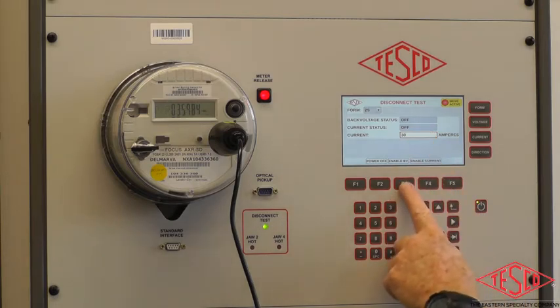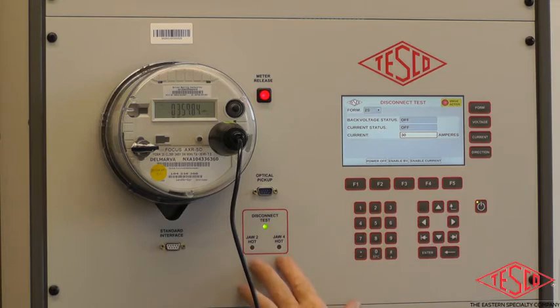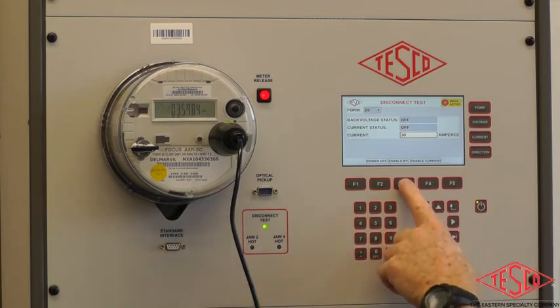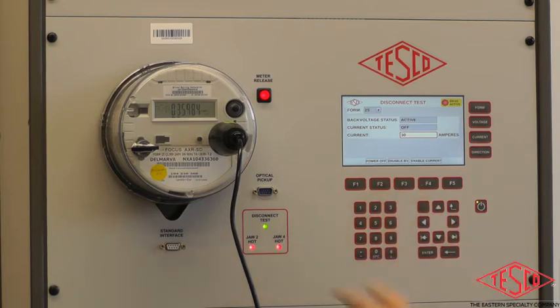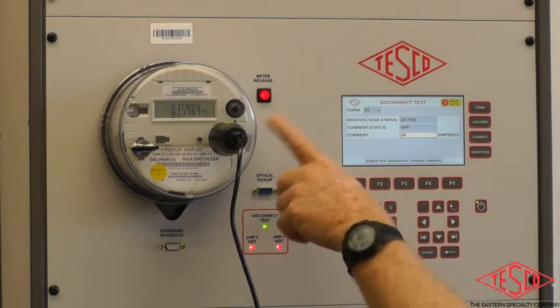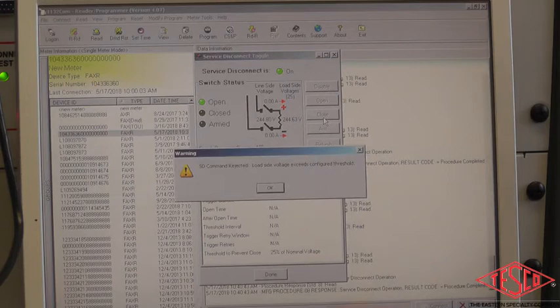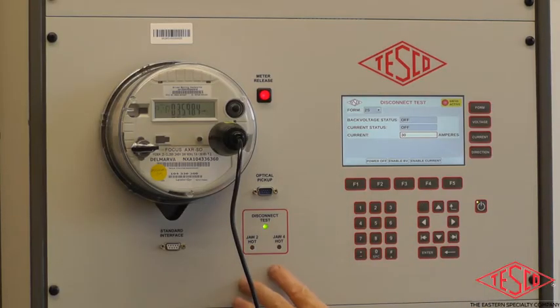So I'm going to enable the back voltage. You'll see the jaws will go hot because now it's simulated that the customer has put a generator or maybe an extension cord from their neighbor and is now applying their own power there. So this circuitry in the meter will see this, and if you try to close on it, it rejects it and says no, there's a back voltage. So now I can disable the back voltage. You'll see it'll return to the state that it would normally be in, where both the load side jaws are cold. So now we can retry to connect.